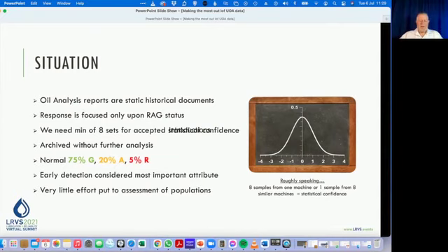So we look at it: if it's red, we do something maybe; if it's amber, we go, okay; and if it's green, we file it. Now the proportion is normally about 75% or two-thirds of the reports we get from our fleets or population should be green, in good order, no significant issues. We'd also expect 20% to be at some kind of cautionary level and 5% requiring some kind of intervention or action. That would be normal. The ideal, of course, is 99% green, 1% action, no reds.